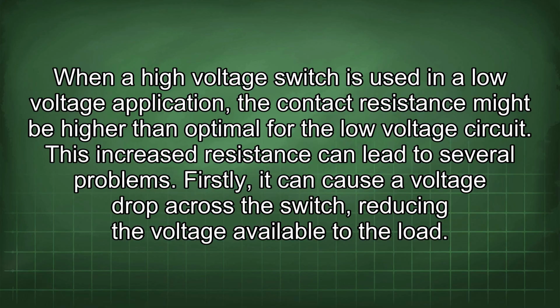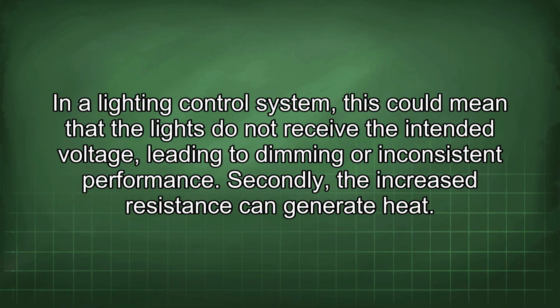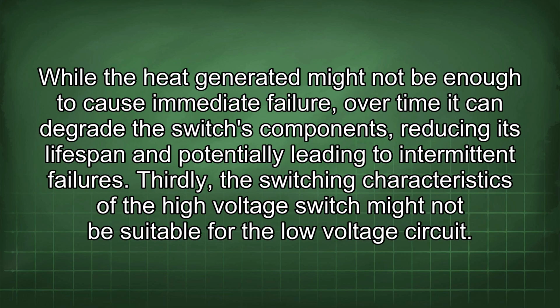Firstly, it can cause a voltage drop across the switch, reducing the voltage available to the load. In a lighting control system, this could mean that the lights do not receive the intended voltage, leading to dimming or inconsistent performance. Secondly, the increased resistance can generate heat. While the heat generated might not be enough to cause immediate failure, over time it can degrade the switch's components, reducing its lifespan and potentially leading to intermittent failures.